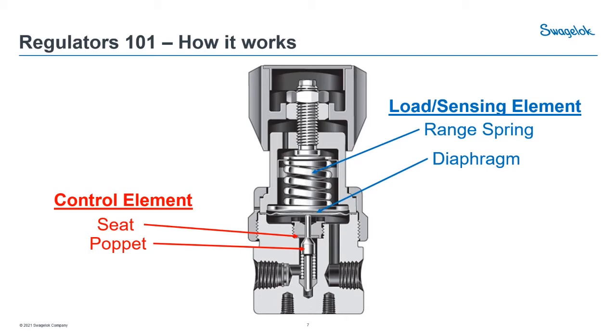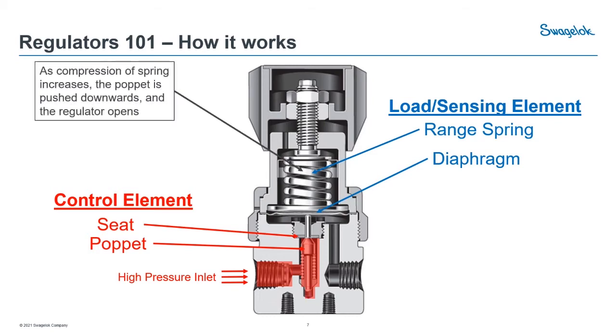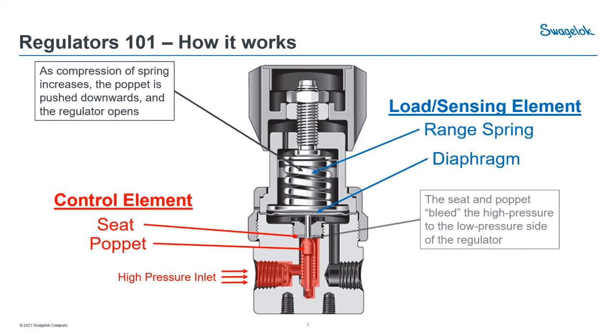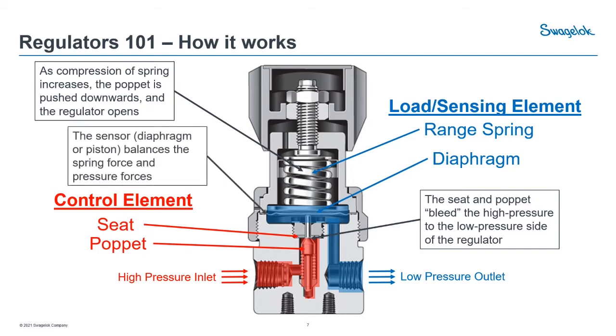Here's how these actually work. Our high inlet pressure enters the regulator. You then start to turn that handle, and as you turn it, you compress the spring. That moves the poppet downward, and eventually your regulator opens. As it opens, you start to bleed that high pressure fluid over to your low side. Once it reaches the low pressure you had set, the regulator moves into self-actuating mode, and the diaphragm or piston — depending on which model you have — balances those forces together to maintain the pressure you had set.